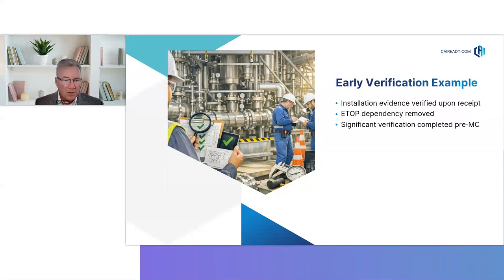Calibration certificates are only one small piece of the WFI loop. For a stick-built WFI system, many critical verifications can occur before mechanical completion: material certificates for product contact piping, weld logs and orbital welding parameters, borescope inspections, surface finish records, pressure test results, and installation checks for valves, spray devices, and instruments. These verifications are tied to specific components and segments of the loop, not necessarily to overall system completion.